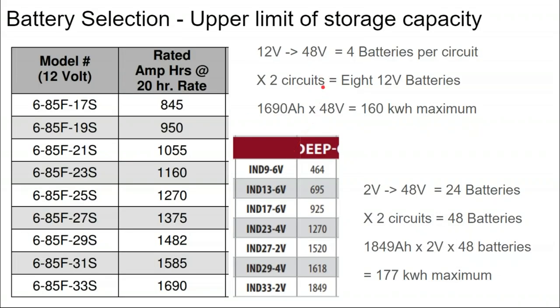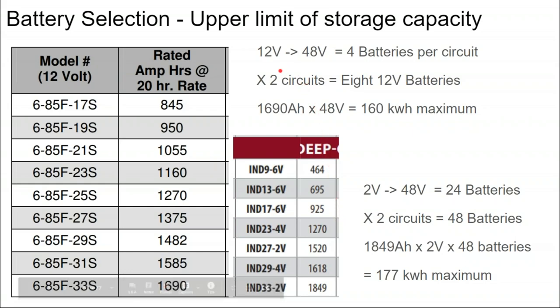Looking at this particular market-leading industrial flooded lead-acid battery manufacturer's most energy-dense product, we're looking at a 12-volt battery having 1,690 amp-hours in their 12-volt configuration. So at 48 volts times 1,690 amp-hours, we're looking at 160 kilowatt-hours of lead-acid storage—about the most you can fit onto one circuit of batteries.